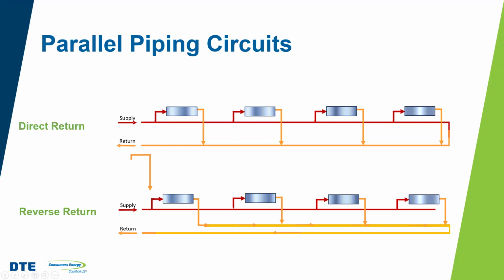So with the direct system here, you can see that the first emitter is closest to the pump, to the boiler, what have you. And the distance between adjacent branches could vary significantly. This could cause significant, high head losses, which need to be accounted for when we design the system. Also, the last emitter is farthest from the pump, so it may have a lower flow. That lower flow is going to be less heat output, so this too needs to be accounted for in the design. You can do that with some balancing valves that can correct for that, or we can use the reverse return system.